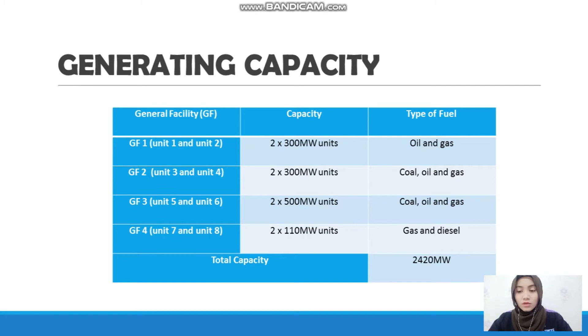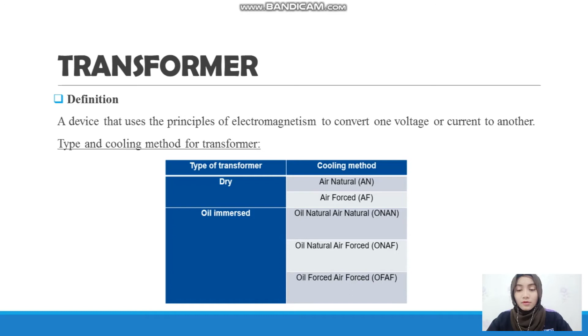Next, we go into training activities or daily routine. A transformer is a device that uses the principles of electromagnetism to convert one voltage or current to another. There are 2 types of transformer: dry type and oil immersed type. For dry type, there are 2 cooling methods: air natural and air force. For oil immersed type, there are 3 cooling methods: oil natural air natural, oil natural air force, and oil force air force.